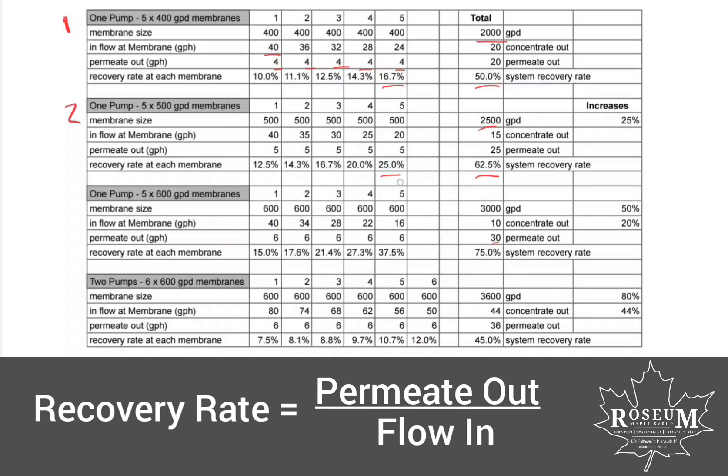This recovery rate number is fine, but you get much higher than that and it can start to be a problem. The reason you want your recovery rate low: if you think about it — a membrane has sap coming in and permeate going through — if you don't have enough flow going along the membrane, the sugar molecules can build up on it and there's nothing to push them off. That's what we call membrane fouling. You want good flow across the membrane, not just flow through it, to keep moving those sugar molecules and other particles off the membrane so it doesn't plug up and slow the amount of permeate that can come through.